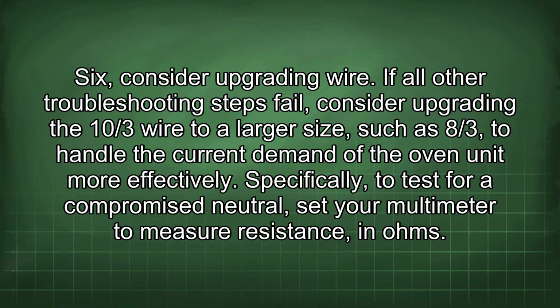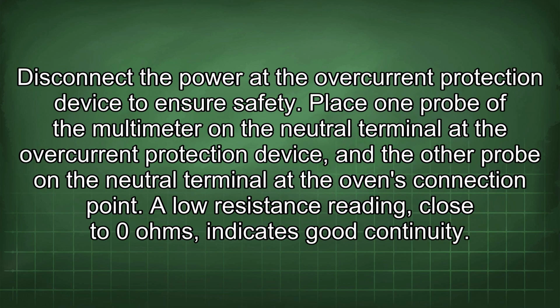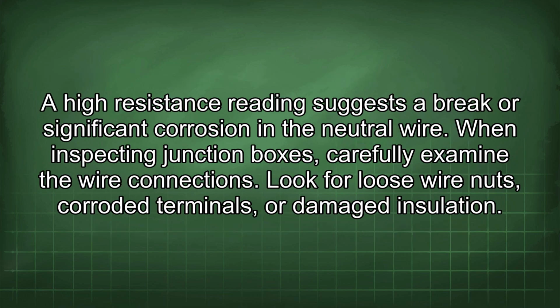Specifically, to test for a compromised neutral, set your multimeter to measure resistance in ohms. Disconnect the power at the overcurrent protection device to ensure safety. Place one probe of the multimeter on the neutral terminal at the overcurrent protection device and the other probe on the neutral terminal at the oven's connection point. A low resistance reading, close to 0 ohms, indicates good continuity. A high resistance reading suggests a break or significant corrosion in the neutral wire.